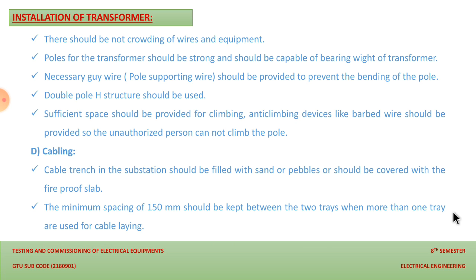The next point is cabling. The cable trench in the substation should be filled with sand, because it provides proper insulation, or pebbles, or should be covered with a fireproof slab. So that provides insulation against fire. And a minimum spacing of 150 should be kept between two trays. So yes, cable trays are there in the substation. This is the standard distance that we should keep in mind while using cable trays. If more than one tray is used for cable laying, then we should provide a spacing, say 150, between each tray, which is advisable to protect our system and utility from danger in future.